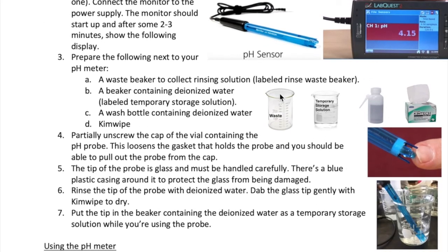Now, get the following four items next to your pH meter. A beaker to collect rinse waste. A beaker filled with deionized water to serve as a temporary storage solution for your pH probe. A wash bottle and then a box of Kimwipe.